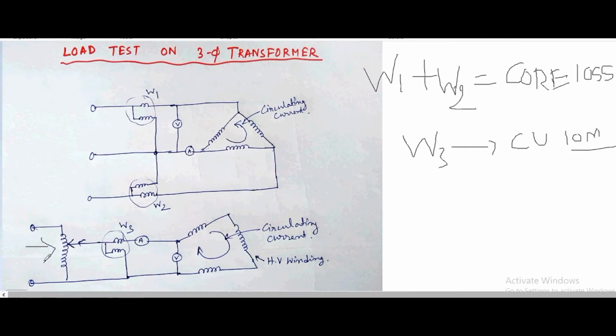And when the voltage is injected into the secondary to circulate the rated secondary current, at the same time the current will circulate in the primary winding, in the closed delta, but the W1 and W2 readings will be unaffected or unaltered. So this experiment will give W1 and W2 as the core loss, whereas W3 will give us the copper loss of this three-phase transformer.